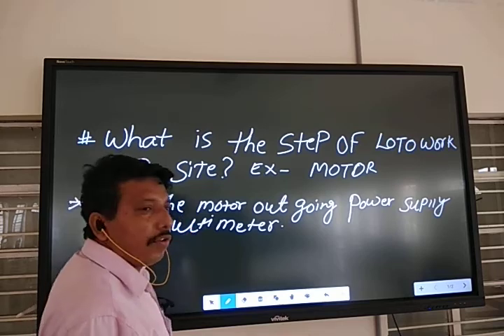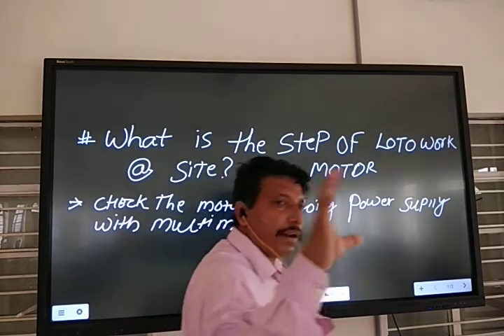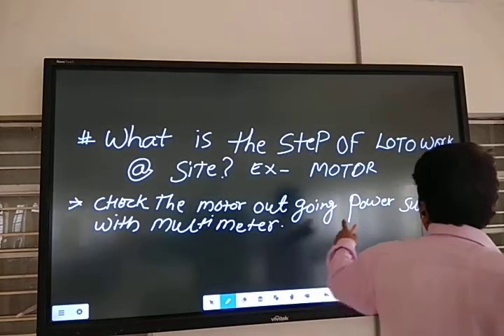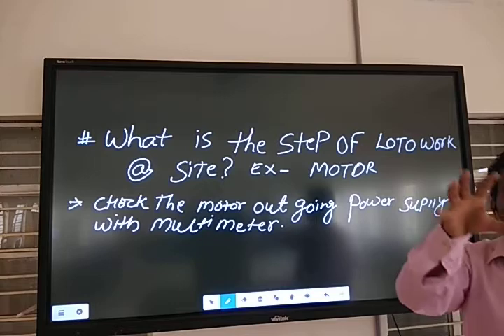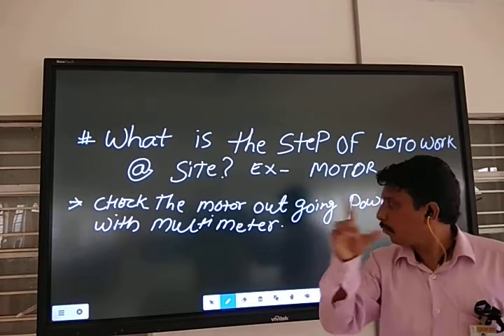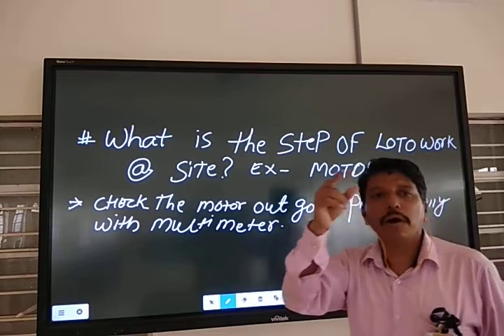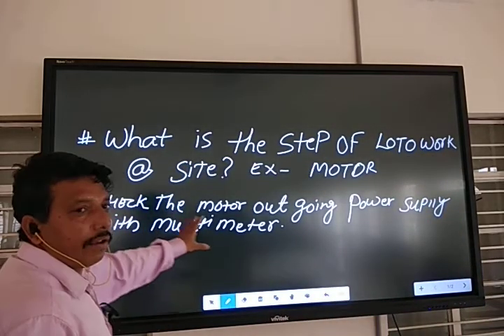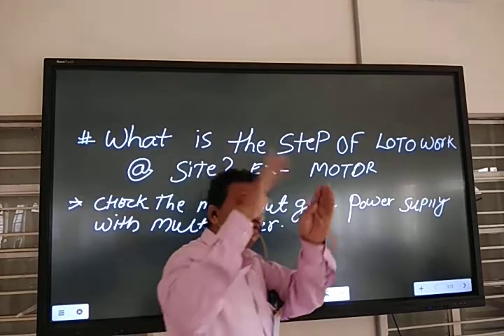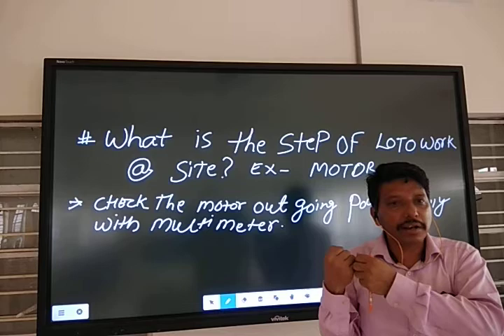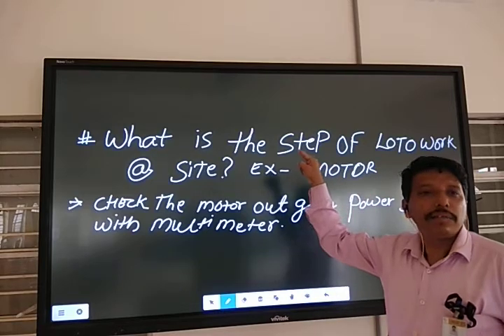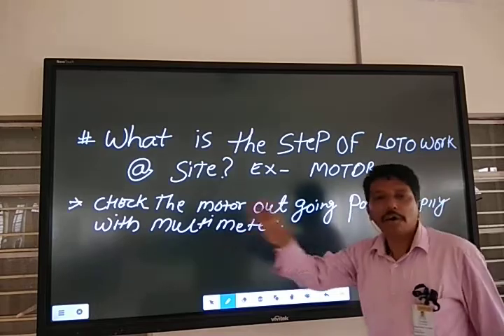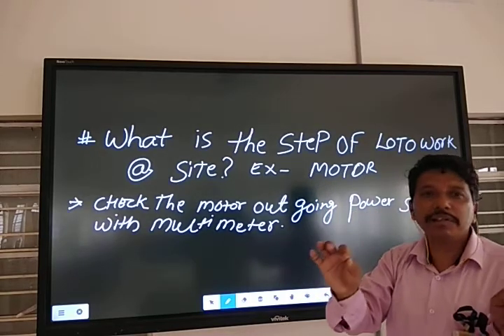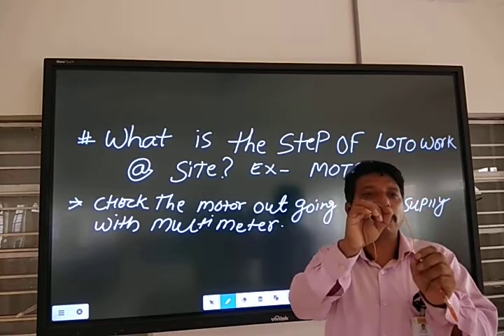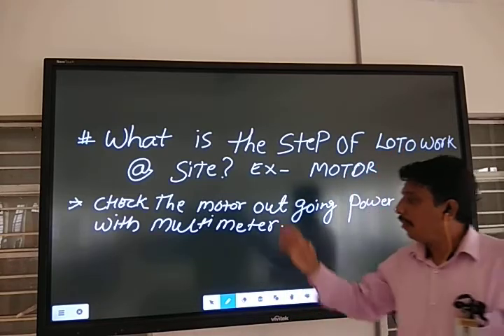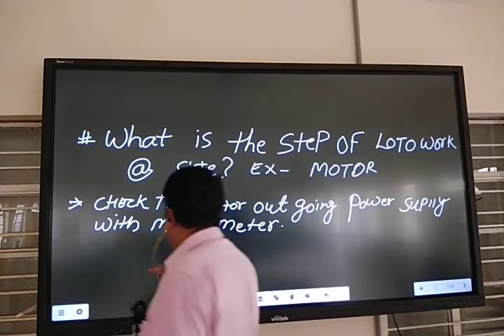So during lockout work, you should check with your multimeter whether there is power or not, to confirm you put the correct breaker switch off. Close the main supply, then come to the working area with the motor. If the power is not there, this means the correct breaker is off, the correct switch is off. If so, you can return to panel mode.